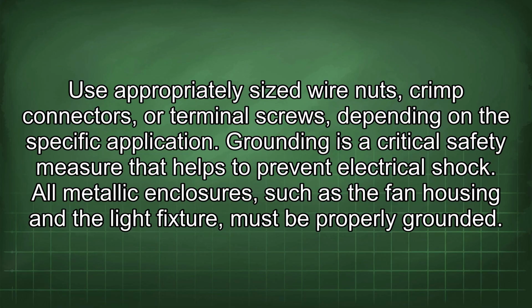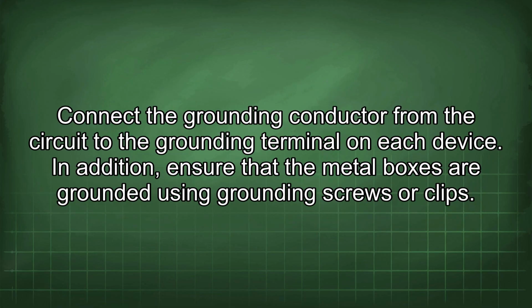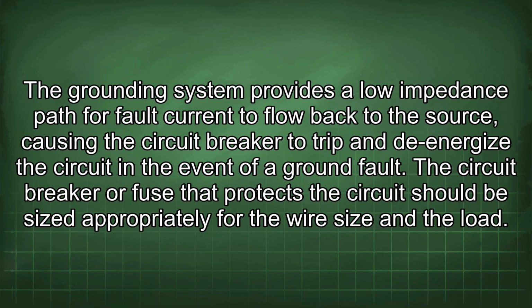Grounding is a critical safety measure that helps to prevent electrical shock. All metallic enclosures, such as the fan housing and the light fixture, must be properly grounded. Connect the grounding conductor from the circuit to the grounding terminal on each device. In addition, ensure that the metal boxes are grounded using grounding screws or clips. The grounding system provides a low impedance path for fault current to flow back to the source, causing the circuit breaker to trip and de-energize the circuit in the event of a ground fault.